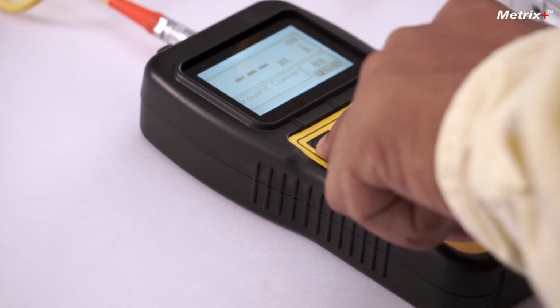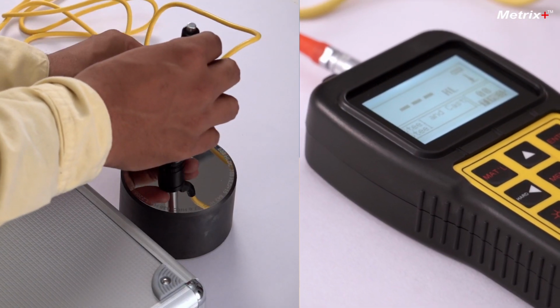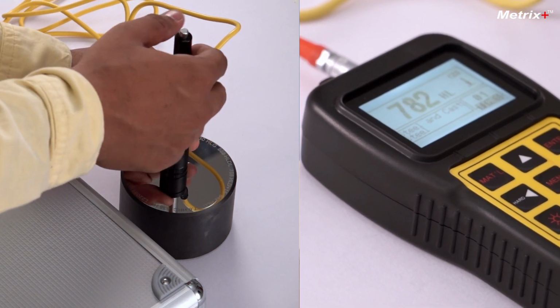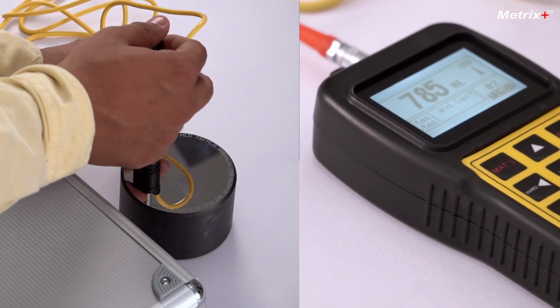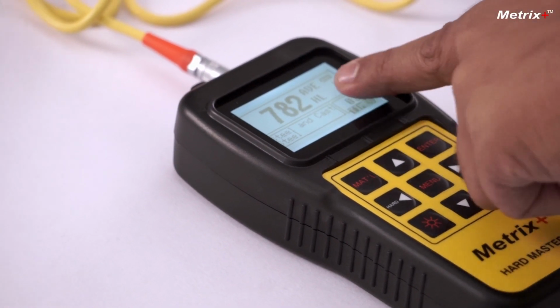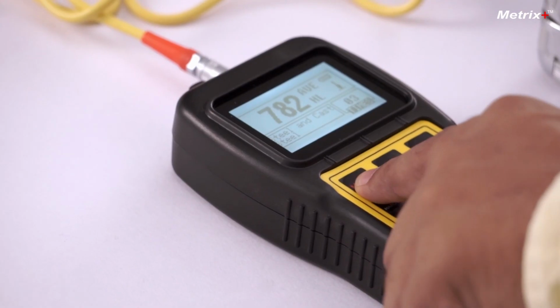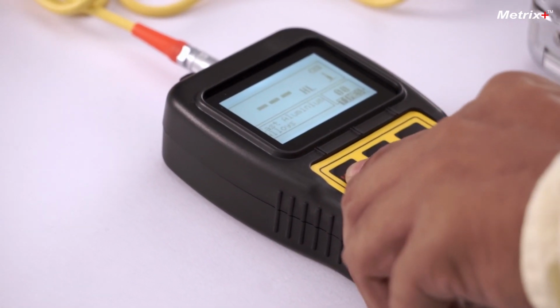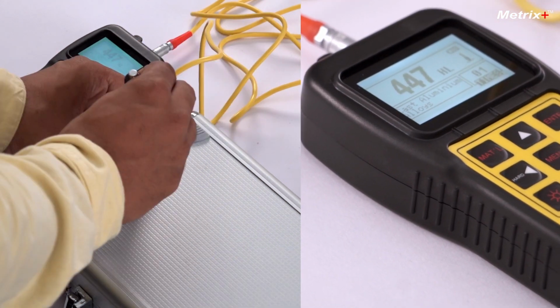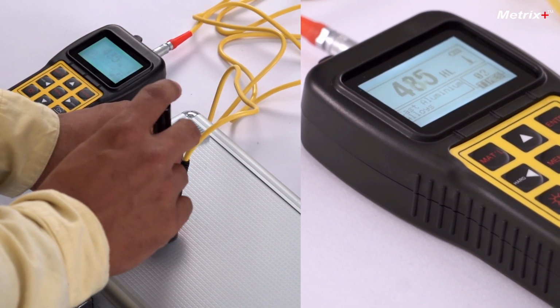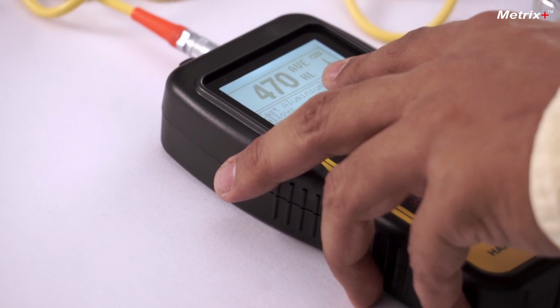Also, you can calibrate it on your material. Like for example, you have your own sample with a known HLD value, so you can calibrate it on that to get accurate values on the same material. Because this is steel, this calibration might not exactly work on, let's say, aluminium or brass or other alloys. So for that, it's recommended that you calibrate on the material of your sample. So now we saw how to operate this instrument and calibrate it to get accurate hardness values on your material.